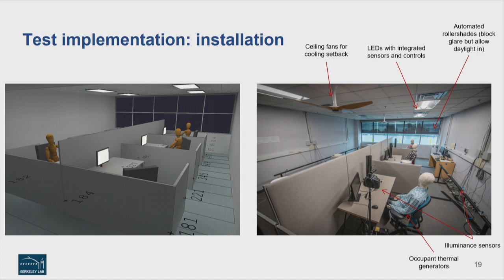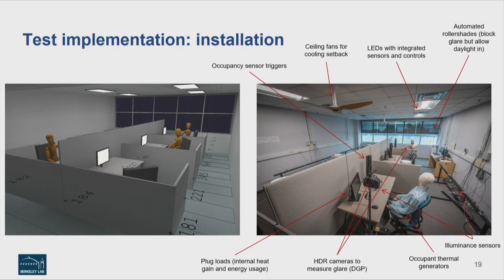We have occupant thermal generators - mannequins with heat tape around them that emit a heat signature similar to a human body, an ASHRAE-defined standard human body, roughly 100 watts of heat if I had to guess. Then there are occupancy sensor triggers, and high dynamic range cameras that do daylight glare probability analysis - I'll show some images from those in a minute. The plug loads provide internal heat that needs to be managed by the HVAC system, and we're also controlling those with an optional feature that does plug load control.